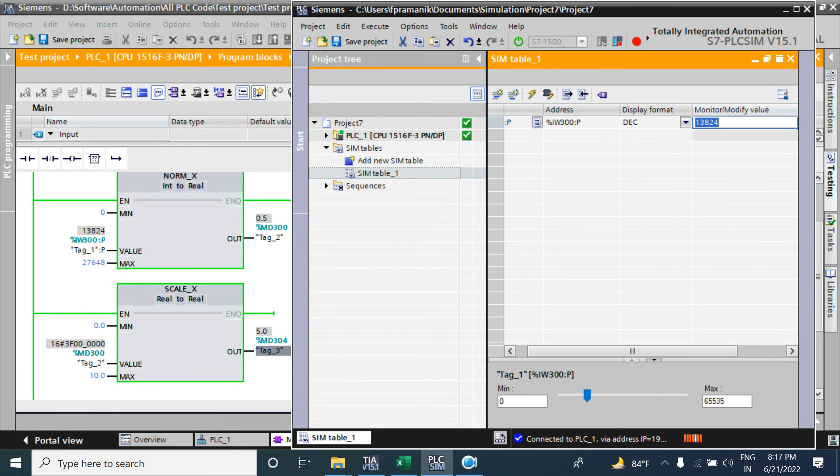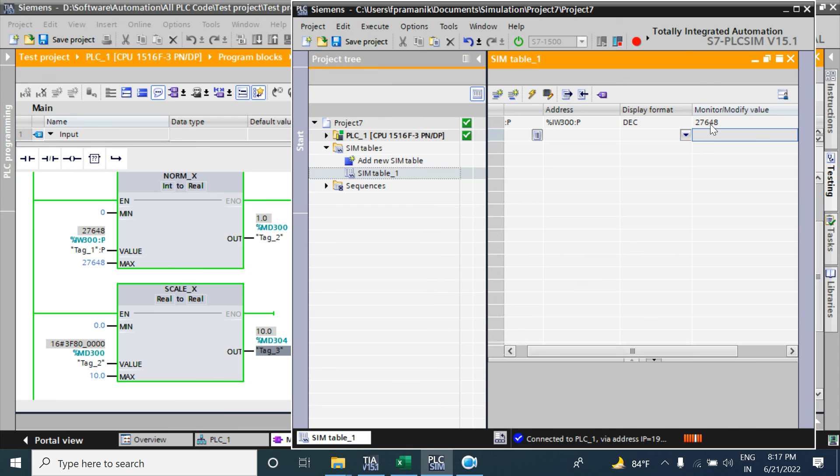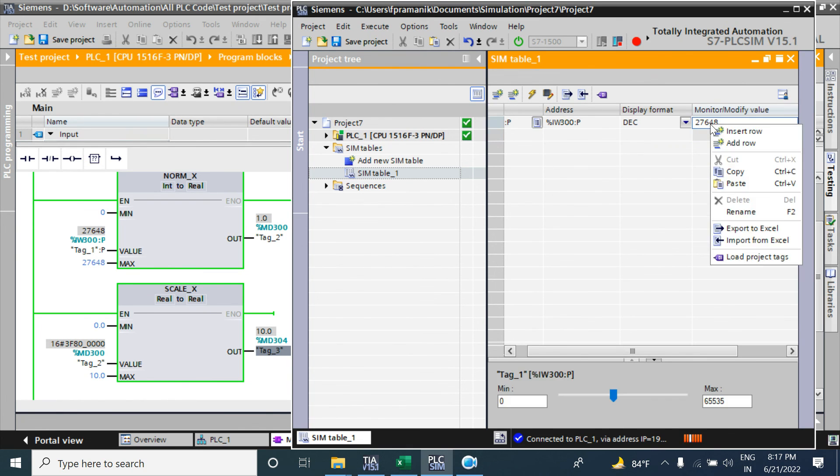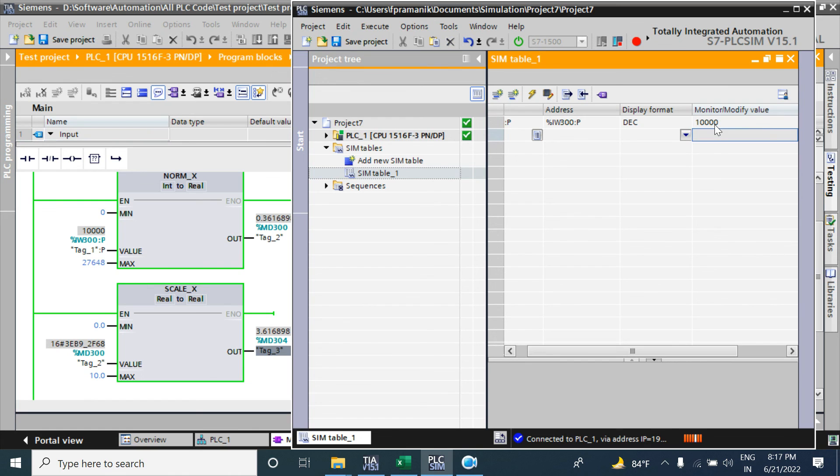First I will give the full range 27648, then value will be 10 bar if the 20 milliamps comes. That means it is 27648 integer value. So if I give 10000, it's near about 50 percent or not, less than 50 percent because 50 percent is 13000.